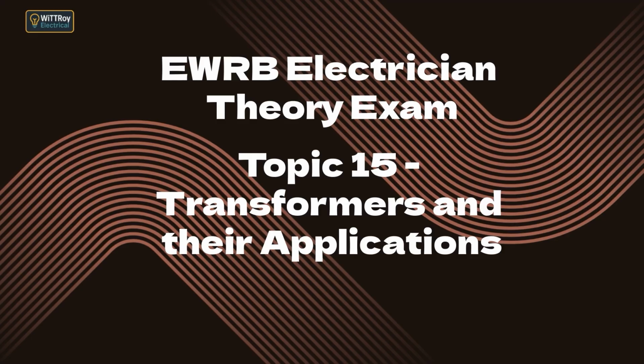15.2 Voltage transformers, VTs, PTs. 15.2a Describe a voltage transformer, its operation and applications. A voltage transformer, VT, steps high system voltages down to safe levels for metering, protection relays, and instrumentation. It operates like a normal transformer but is designed for accuracy and safety. VTs are used in substations and switchboards to measure high voltages indirectly.